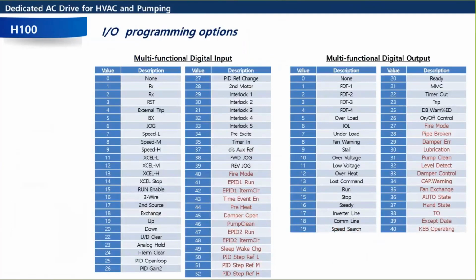Okay, so here is all of the programming options available for your I/O. So thinking back to that first slide, we had P1 through P7 for our inputs. That's everything on the left right here for digital inputs. So we have forward, we have reverse, we have a reset, which is a remote reset, external trip, we have speed low, medium, high, we have accel, decel switches. You could flip a switch on and it'll go to a different accel or decel rate. Run enable, like a safety interlock or something.